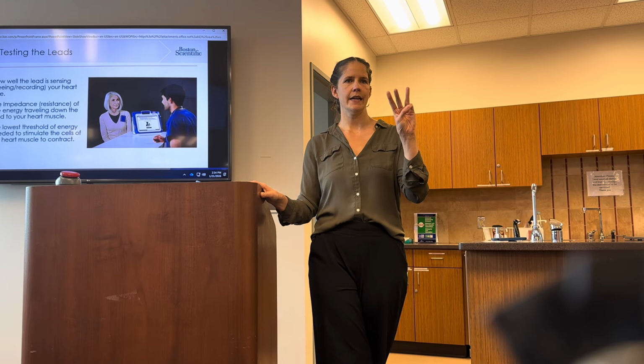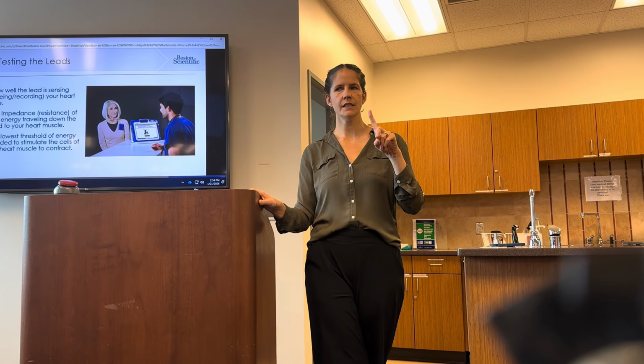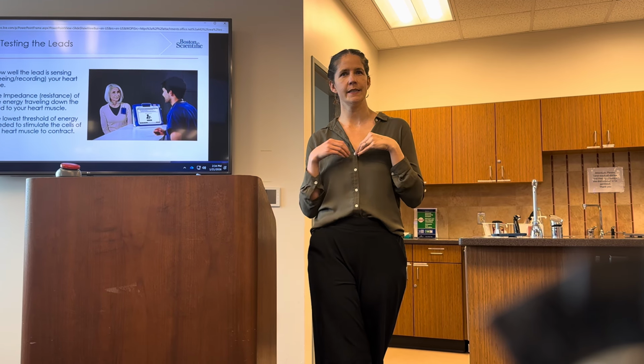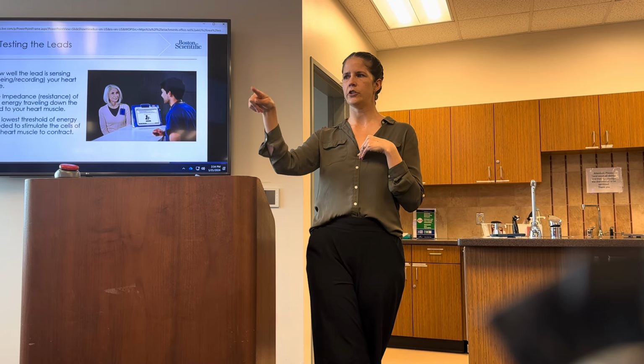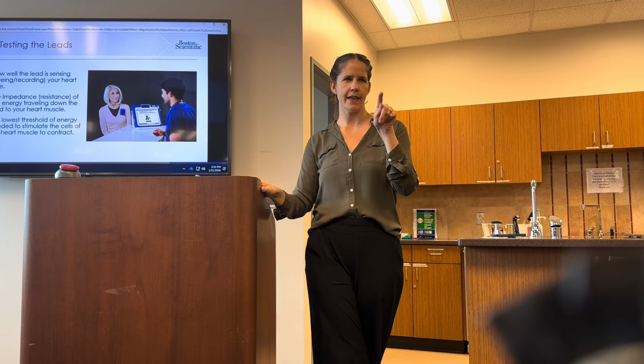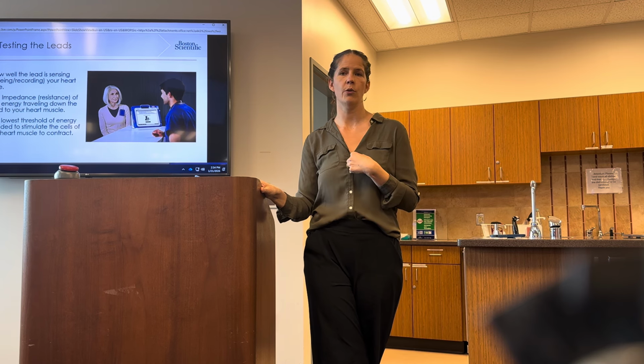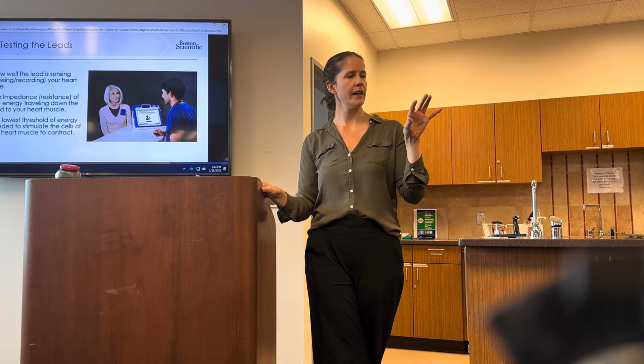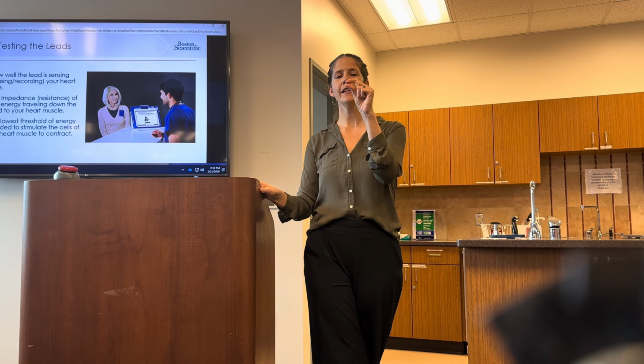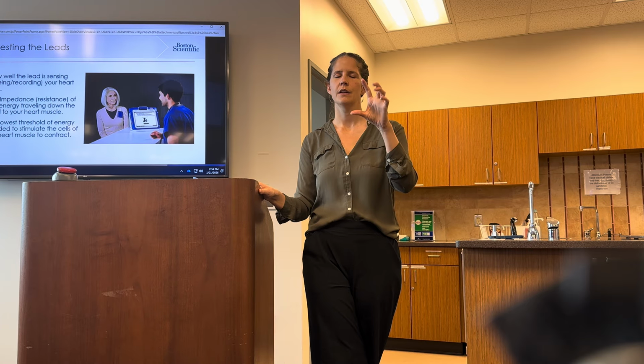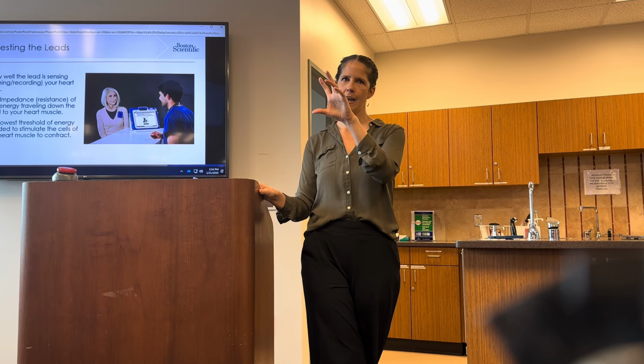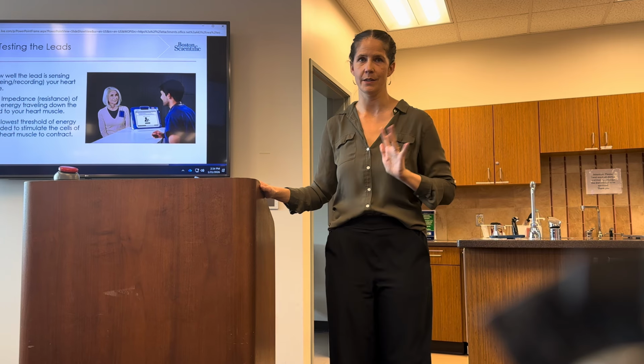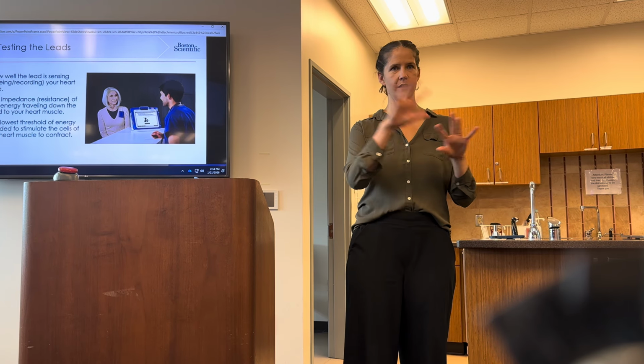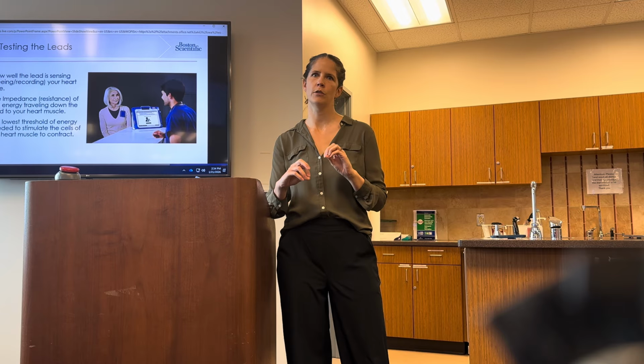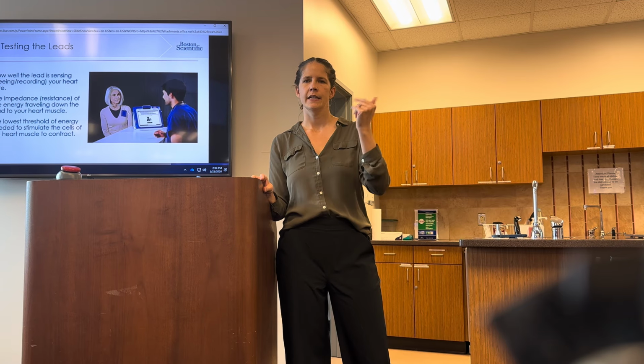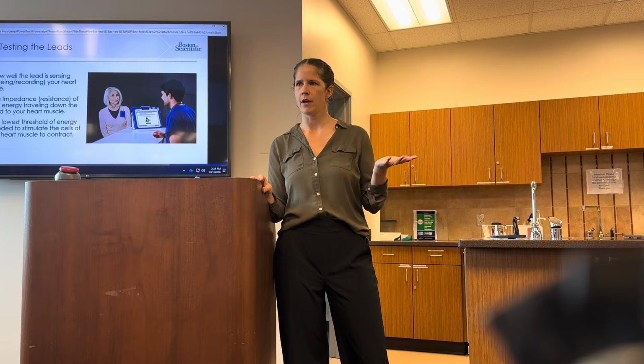So we do 3 main tests on these leads. One is how well is that pacemaker defibrillator lead seeing my heart rate? When you see a little EKG, it's looking at that electrically on the inside. So it'll show us, is it seeing that heart rate? It has a little measurement. If it's really, really little, like 0.1, we're like, that's pretty small. 2 millivolts we're talking about, 5 millivolts. These are all numbers. We work a lot on numbers, and when you hear us in the clinic, we talk in a lot of milliseconds, millivolts, volts. Basically, is a pacemaker seeing your heart rate properly or not?